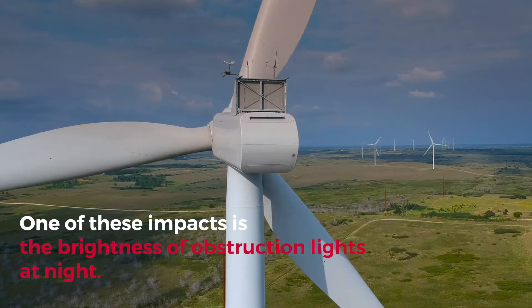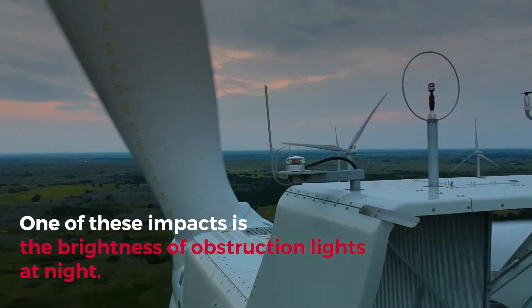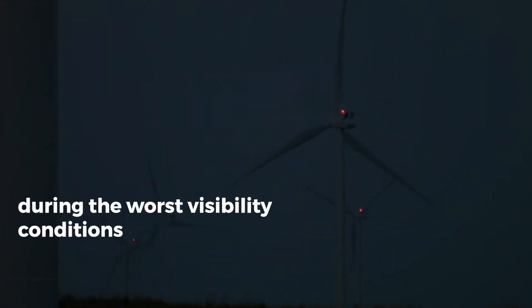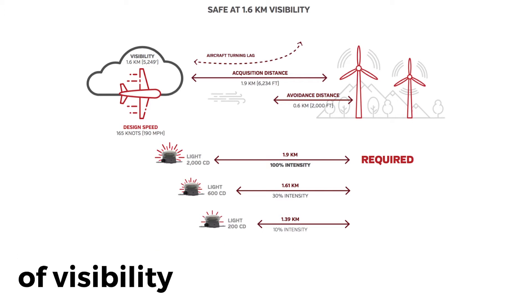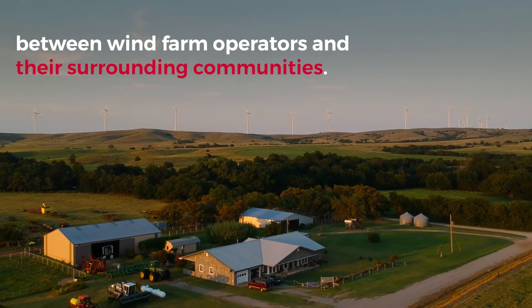One of those impacts that can be managed is the brightness of obstruction lights at night. The Federal Aviation Administration requires obstruction lights to produce 2,000 candela of intensity during the worst visibility conditions. Visual flight rules dictate that a pilot is allowed to fly with a minimum of one statute mile of visibility. The brightness of the lights is increasingly becoming a point of contention between wind farm operators and their surrounding communities.